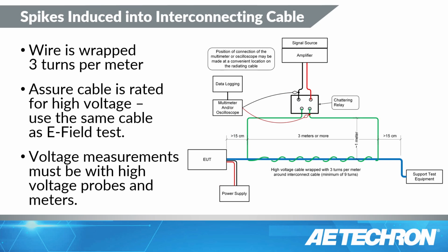When we get into doing the induced spikes into the interconnect cables, again, you're going to be doing this 3 turns per meter. So what I like to do, and I recommend this to my clients, is use that same cable used for high voltage. At this point, you can disconnect it from your resistor or whatever termination you might have for safety reasons, and connect that same wire into your chattering relay, which is the other name for the induced spikes test. So the relay coil will use the same wire as the high voltage or the electric field induced in the interconnect cables.